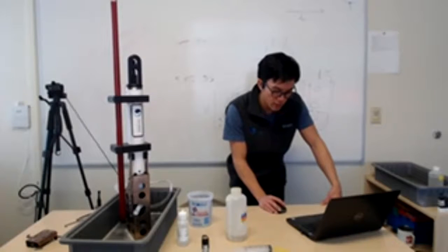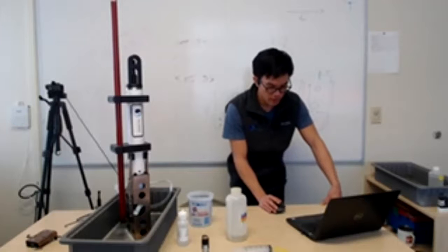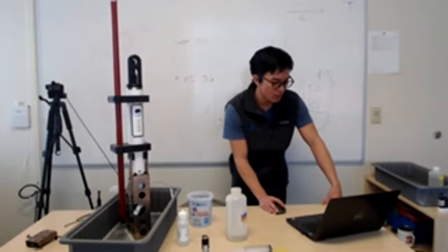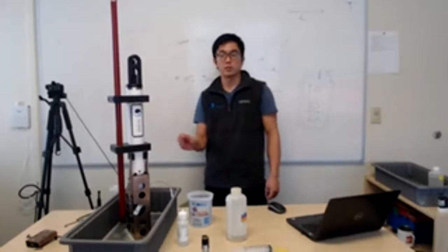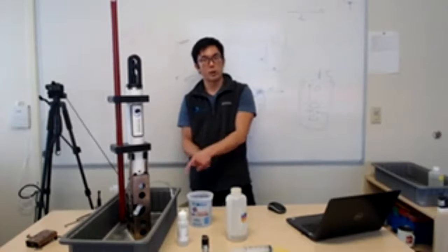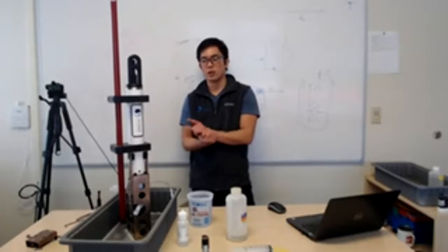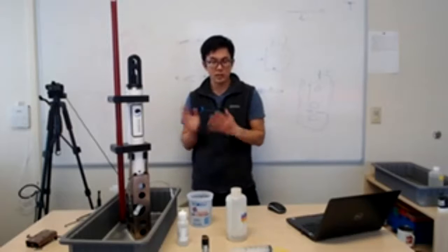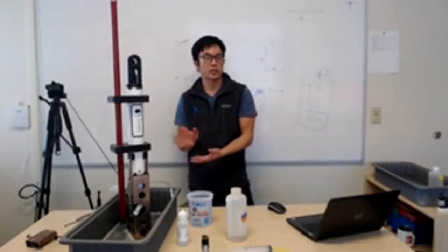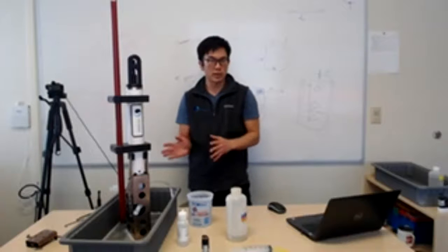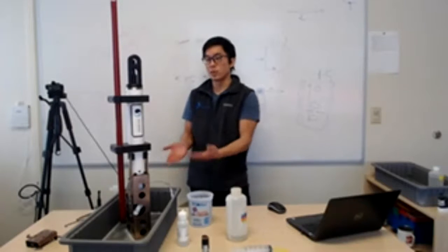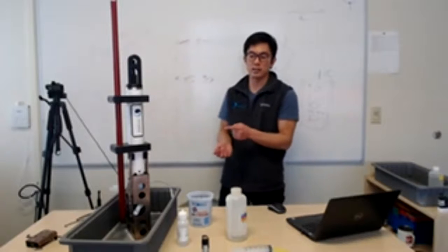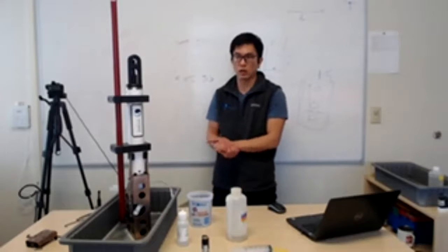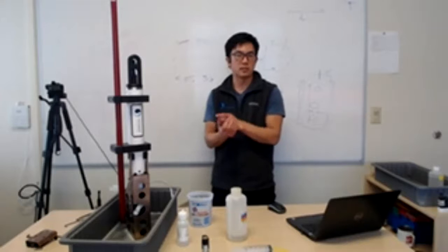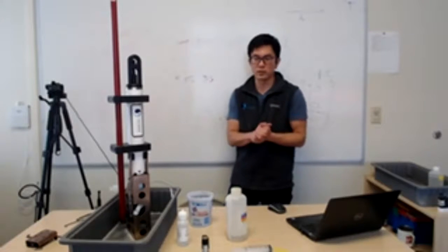Okay, we have another question. Can the pump be disabled for certain applications, such as profiling CTD deployment, so that I can get quick sampling for CTDs only? The HydroCAT EP is not a profiling CTD. If you try to profile with this instrument, the data you get from it will not be good. This is designed to be a moored multi-parameter instrument. If you're using it as just a CTD, it's designed to be used as a moored CTD, not to be moving through the water column, not to be exposed to really dynamically changing values in space.